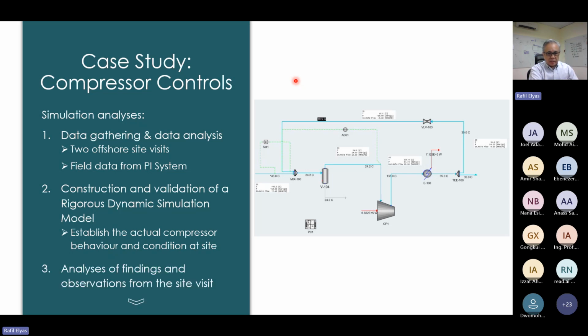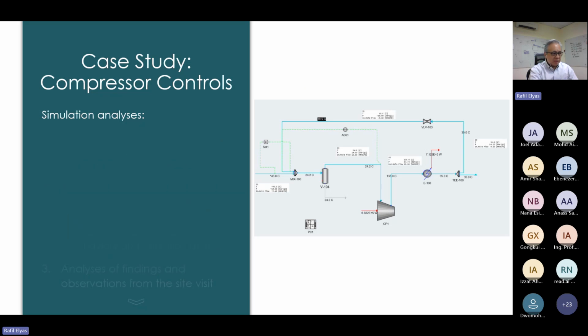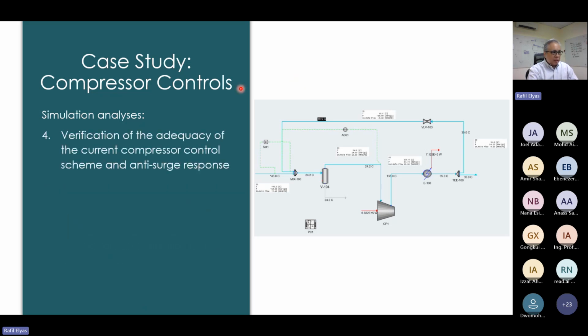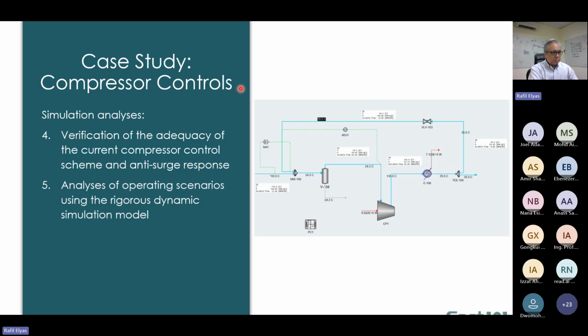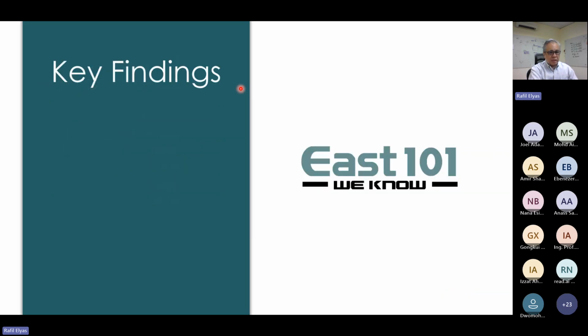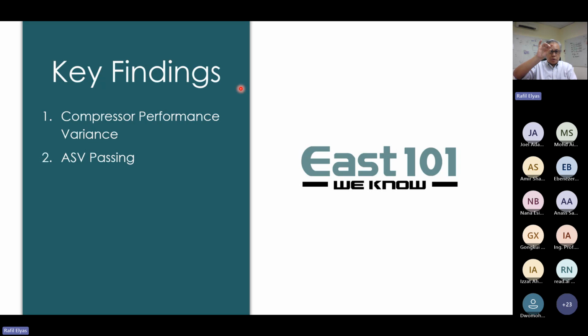So we then performed an analysis of the observations from the site. We also did a bit of anti-surge analysis, which wasn't really much of an issue in this particular case. So here's a finding that we got. One of the reasons that we had maldistribution between the trains was one of the anti-surge valves, even though it showed it was closed, was actually passing. We noticed that on the discharge of the valve, the piping had condensation on it, which indicated there's flow because you get a Joule-Thomson effect.